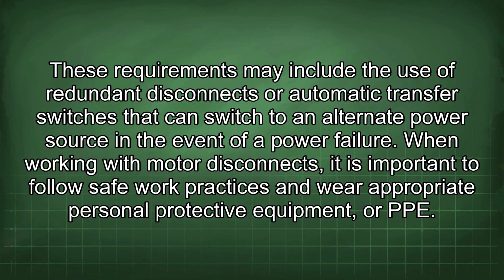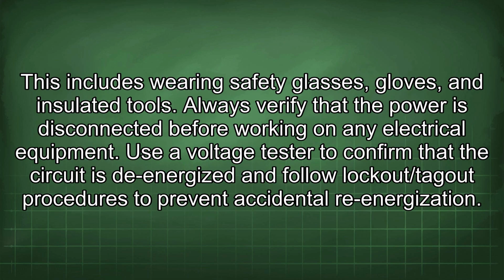When working with motor disconnects, it is important to follow safe work practices and wear appropriate personal protective equipment, or PPE. This includes wearing safety glasses, gloves, and insulated tools. Always verify that the power is disconnected before working on any electrical equipment. Use a voltage tester to confirm that the circuit is de-energized and follow lockout/tagout procedures to prevent accidental re-energization.